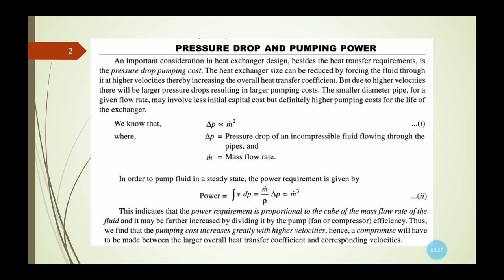Now, in order to pump fluid in a steady state, the power requirement is given by the integral of V dP. It can again be represented as m dot by rho multiplied by delta P. So it is almost equal to mass flow rate cubed. That means we get one mathematical representation: power is almost equal to mass flow rate cubed. It indicates the power requirement is proportional to the cube of the mass flow rate of the fluid.